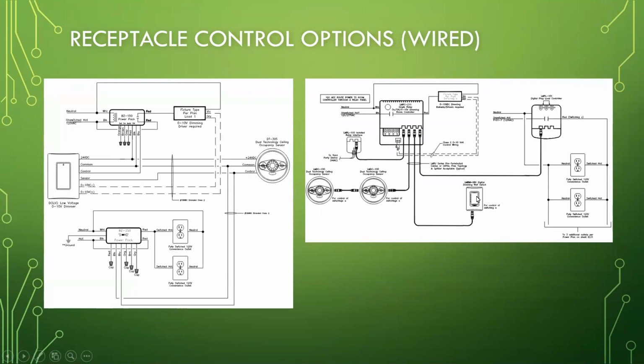If you had a space that had multiple dimmer locations, so you had to have three-way dimming, something more complicated, you can achieve that with their digital systems, room controllers, and digital sensors. Plug load control is just another room controller that's on/off only, and you plug that in just like you would any additional lighting room controller, right into that same device. The sensors are programmed to control both loads together. You're running that receptacle circuit through this room controller and down to your controlled receptacles.